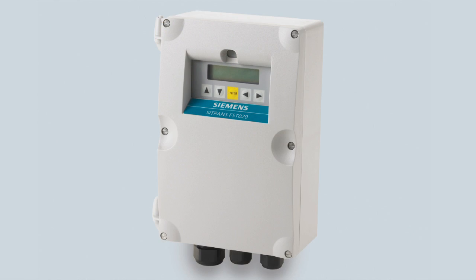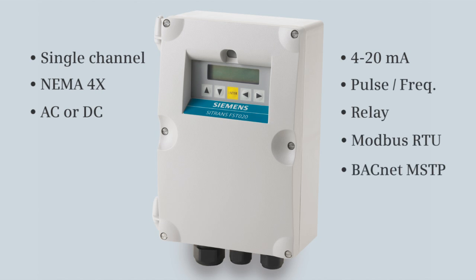The FST020 is offered as a single-channel NEMA 4X in either AC or DC power and includes various outputs. The FST020 outputs include 4 to 20 milliamp, pulse, relay, Modbus RTU, and BACnet MSTP communication, which is used in building automation and control networks for HVAC applications such as heating and cooling.